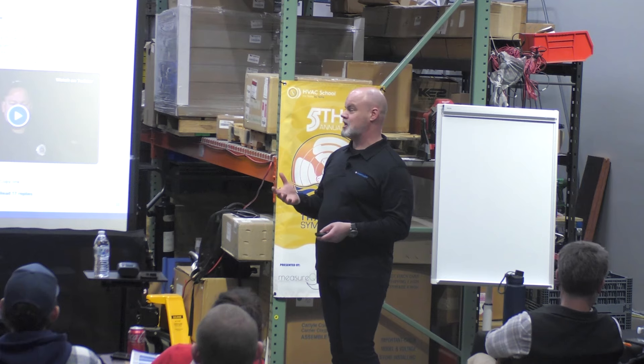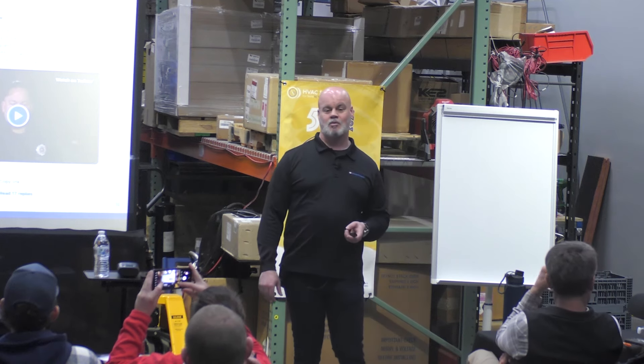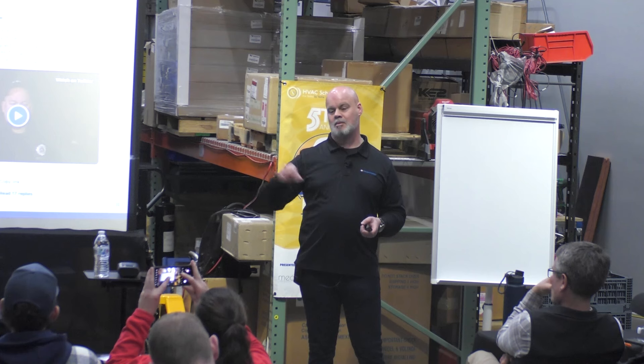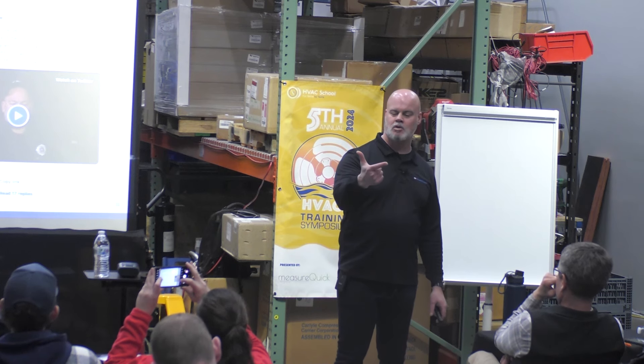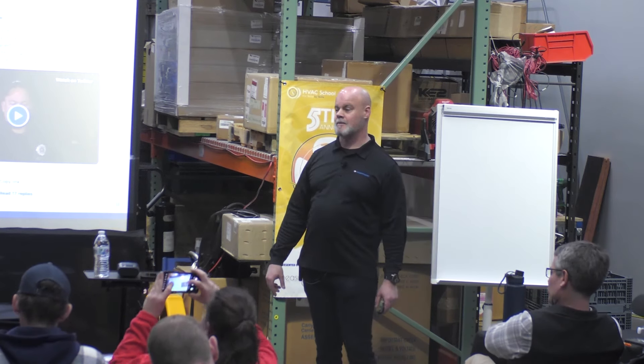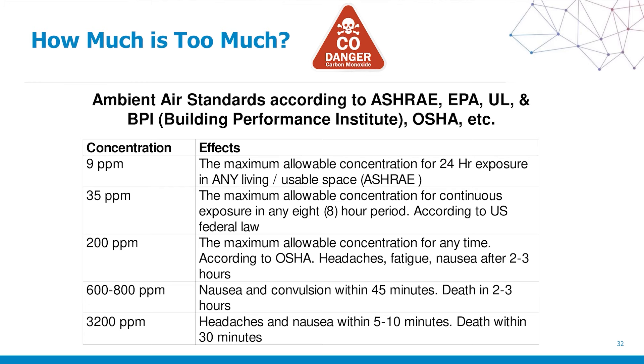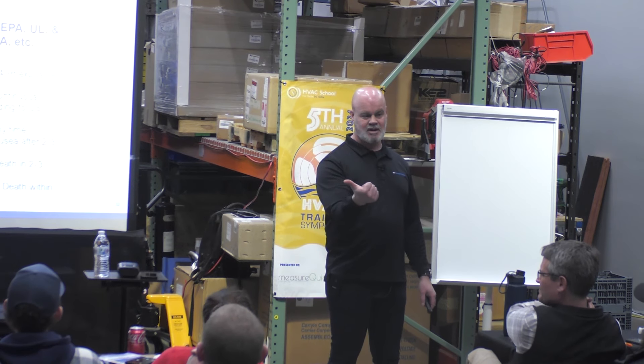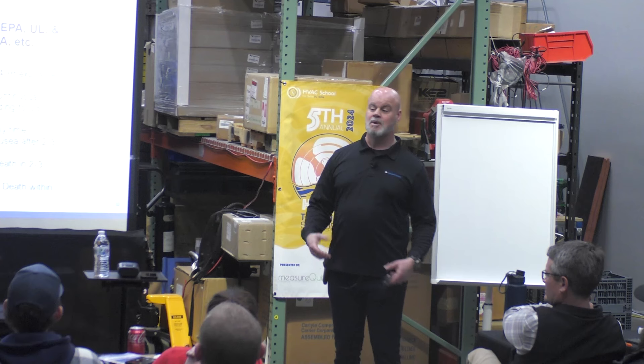I want to keep you safe. If you're relying on your customers' carbon monoxide detectors to keep you safe, you're going after the wrong brass ring. People choose the cheapest CO detection possible because they don't get any social mileage out of it — it's not a nice car or a 4K display. Those detectors go off after 70 to 300 ppm after 1 to 3 hours of exposure — by that time, it already has its hooks into you.